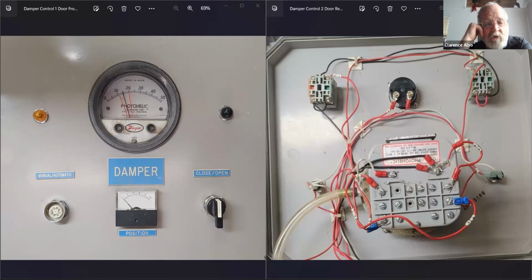If you look at those two needles right there, if you set them too close together, it's going to open and close too much, and that's going to cause oscillation. So you've got to open those up just far enough so you don't have that going on, and then it finds some place in the middle. That's something you have to adjust for when you're thinking about putting this thing in automatic. If it overshoots, widen them out a little bit, then bring them in a little at a time until you find your right spot.